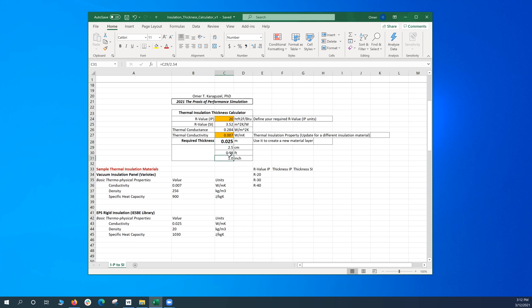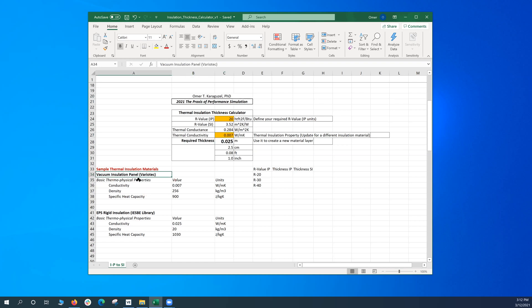So here's an example. I'm looking for R20 R-value for my insulation, and I'm using a specific type of insulation with a thermal conductivity of 0.007, which is the vacuum insulation panel from Variotec, which looks like a very powerful insulation material in terms of thermal resistance capacity. Look at the conductivity, it's a very very low value.